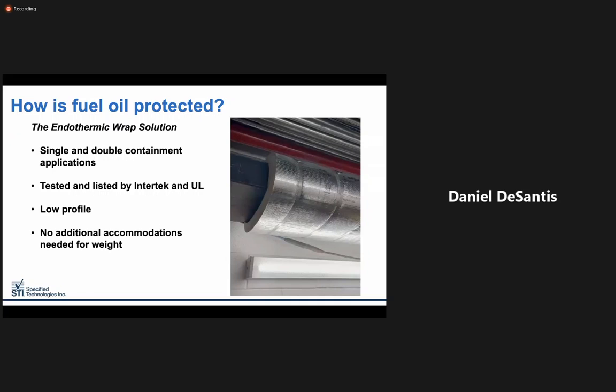Why use an endothermic wrap for fuel oil line? Well, the code tells us that piping, both vertical and horizontal, must be contained in dedicated shafts. These can take up space that could be better served on your project. They're often costly to build if cast in place or CMU are involved.